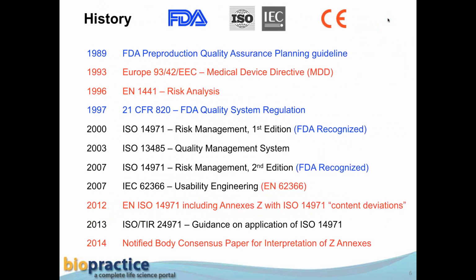FDA in blue. So FDA actually got us going on this in 1989, what we called the PPQA planning guideline, pre-production quality assurance. And it wasn't until 1997 that FDA actually mentioned risk in a regulation. And in this case, risk analysis is the term that they used in 1997. At that time, in Europe, we had EN 1441 for risk analysis. Again, that's a subset of the overall risk management process the way we know it today.